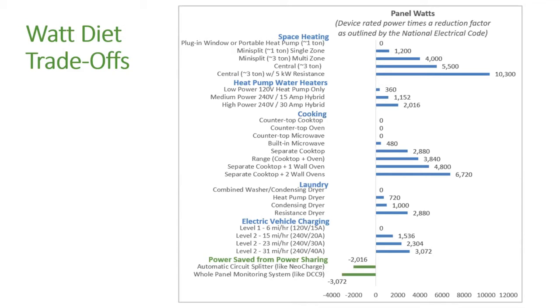We've broken it out by several categories. The top category on the page is space heating—things like that window plug-in heat pump. I bought one of those after reading one of Sean's early guides, and it counts as 0 watts because it's just part of the first 3 watts per square foot. So it doesn't load onto my panel sizing calculation, and the building department won't make me upsize.